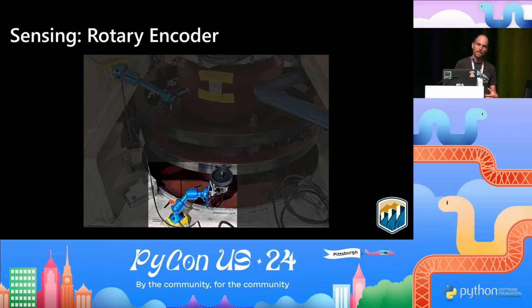This slip ring - remember, we have 250 machines in our fleet, probably more actually, and they're all different - I don't know the circumference of that slip ring. I can measure it with a tape measure, but there's all kinds of stuff in the way, called brush gear, which is how you get current onto the rotor. So tape measures are kind of out. I'll get to how we do this, but I need to learn that drive ratio, and measuring isn't an option.